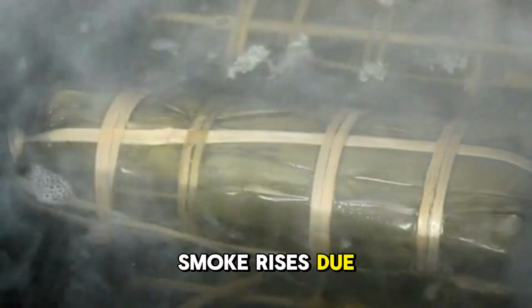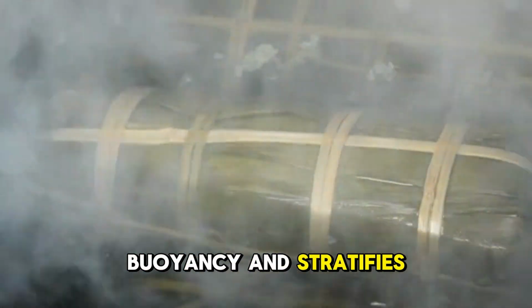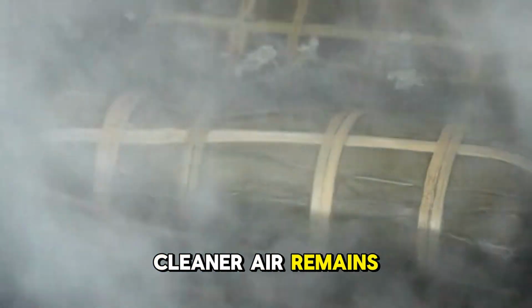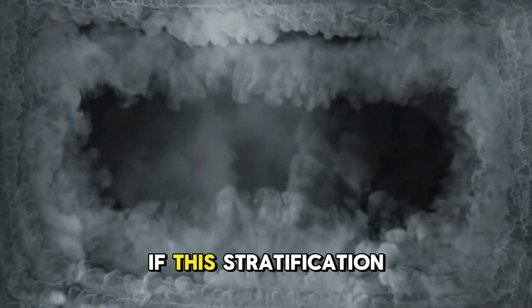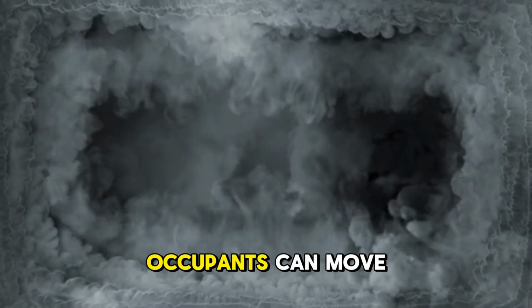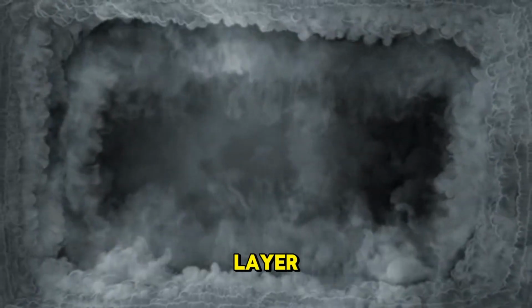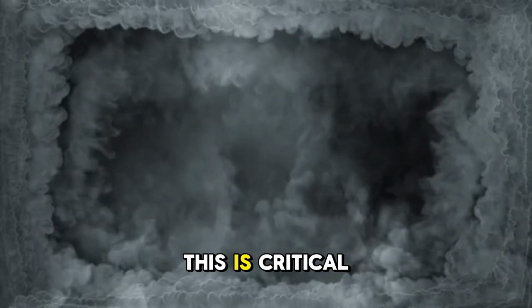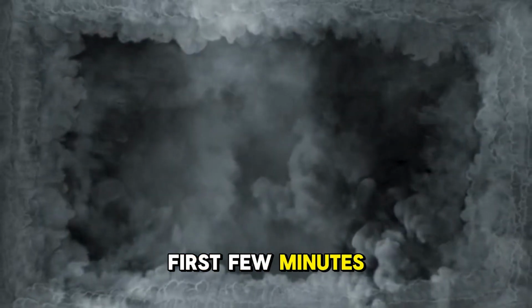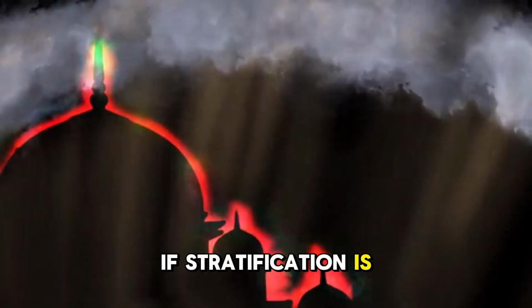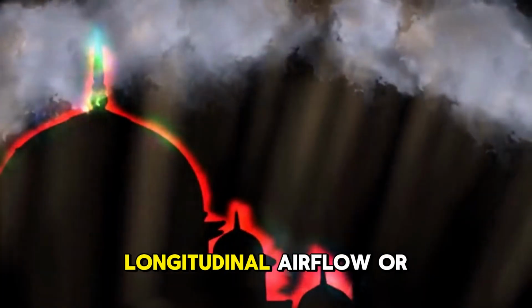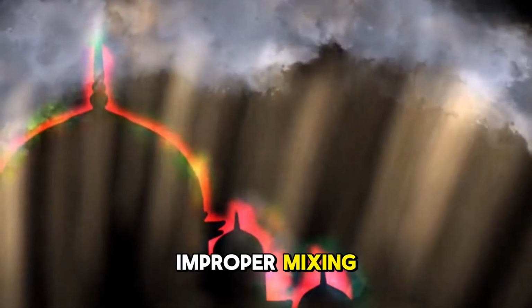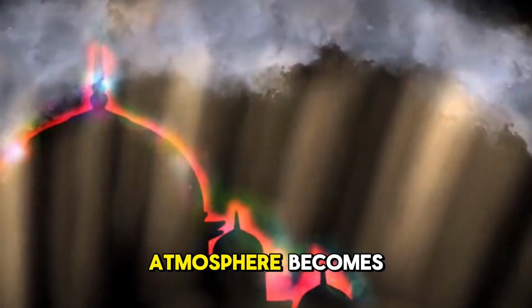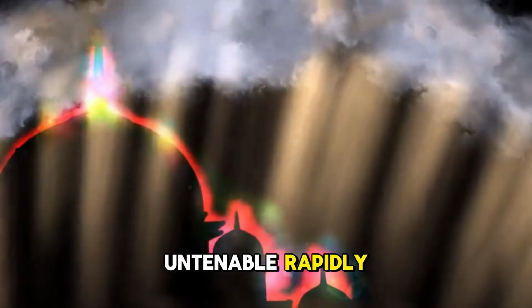Smoke rises due to buoyancy and stratifies. The hot, buoyant smoke layer rises to the ceiling while cooler, cleaner air remains at a lower level. If this stratification is preserved, occupants can move below the smoke layer toward the exits. This is critical for survival in the first few minutes. If stratification is disrupted by strong longitudinal airflow or improper mixing, the entire tunnel atmosphere becomes untenable rapidly.